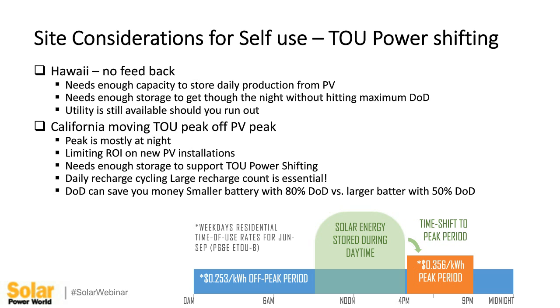California is moving time-of-use to off-peak, PV hours, so make sure you can configure your inverter to support that. You need to contact your local utility company—whether it's PG&E, San Diego, or LA—to make sure they're going to allow you to do this. But you need to have a hybrid inverter that can support it, because all the utility companies are putting together policies for this if they haven't already implemented it. So you want to be prepared to feed it back.